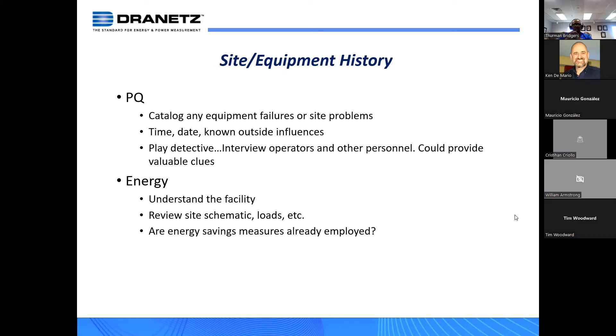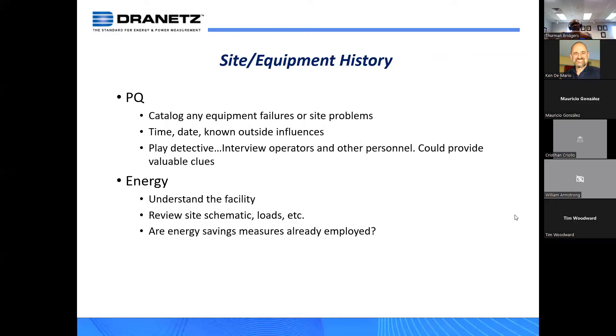Catalog any equipment problems or site problems. For example, if a production line was shutting down at the same time every day, you want to catalog that, including any outside influences. In a lot of cases you want to play detective — interview the operators and other personnel, as that could provide valuable clues. Finding PQ problems is like being a detective: you want to get information from as many sources as you can, which makes the monitoring more efficient and helps establish that consistent correlation between facility activities and actual data recorded by the instrumentation.